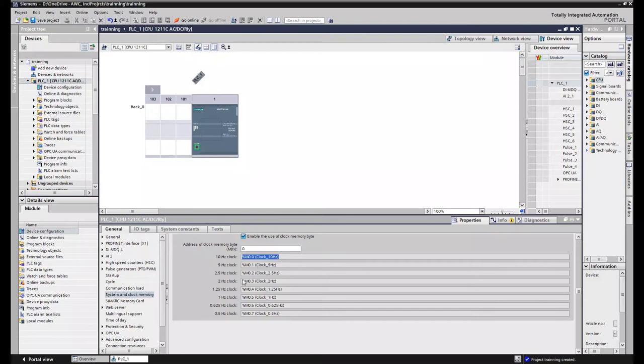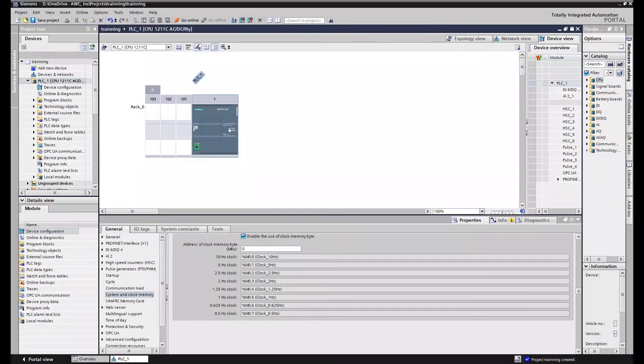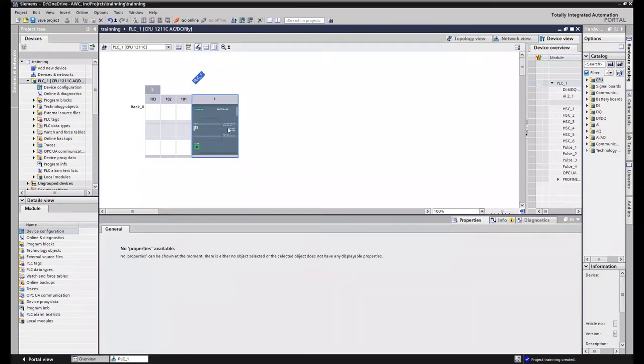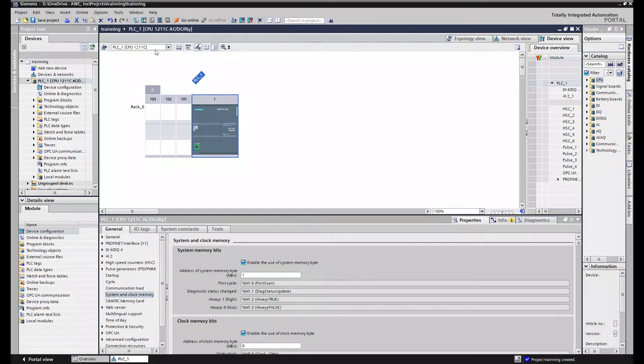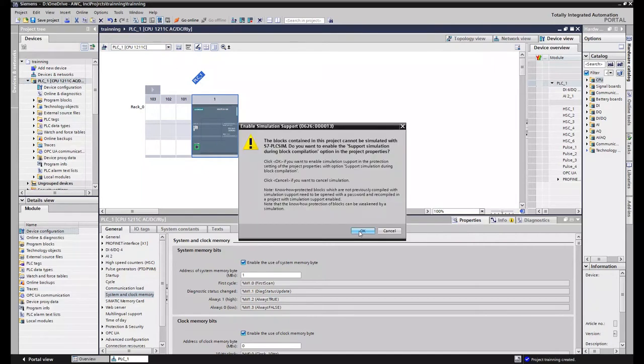So since we have enabled this and this is in the hardware config, this requires a hardware download. So it will stop the PLC. So if you're using an existing PLC and you want to put this on there it will stop it. So if it's a running system you need to be mindful of that. So let's open up our simulator and then let's get this thing downloaded. I'm going to press OK to open up the simulator.